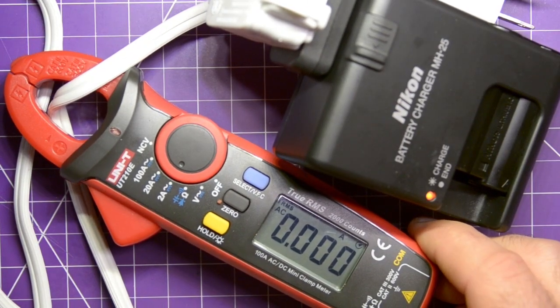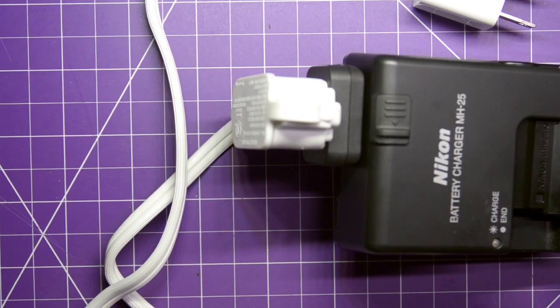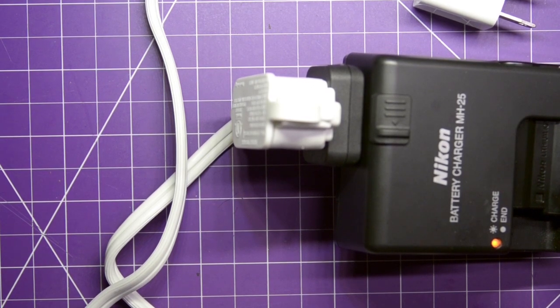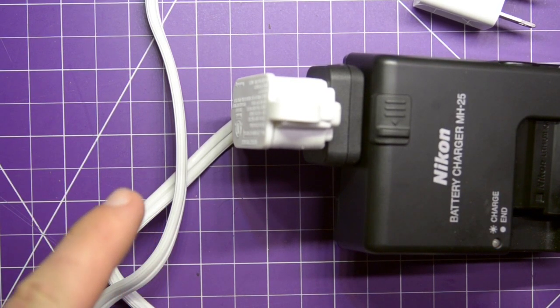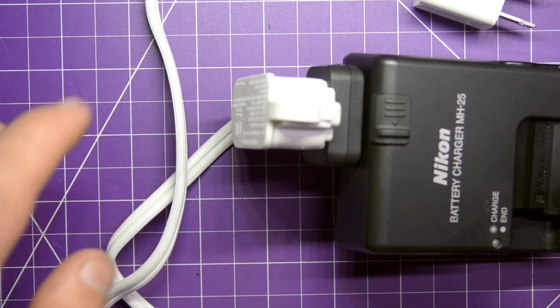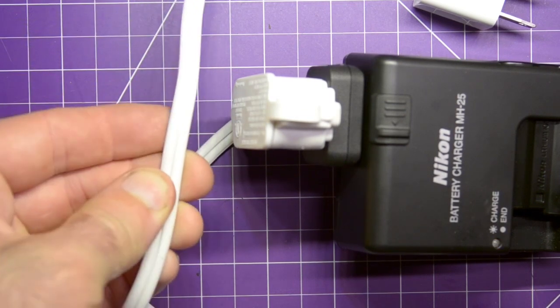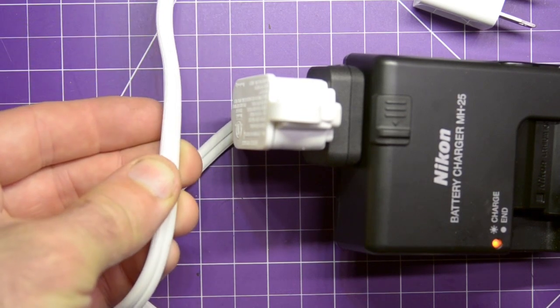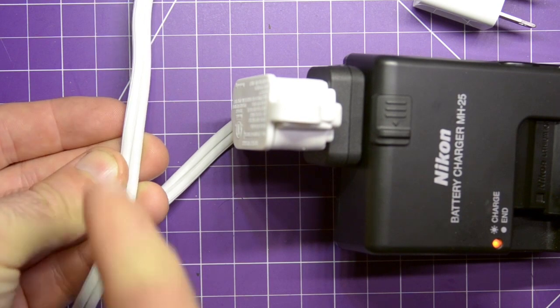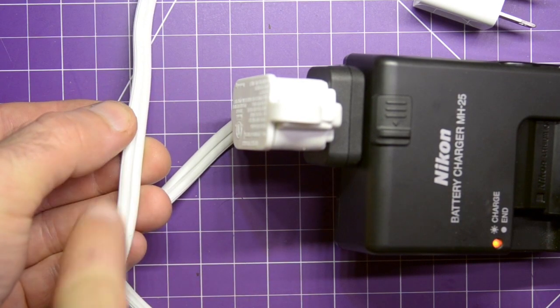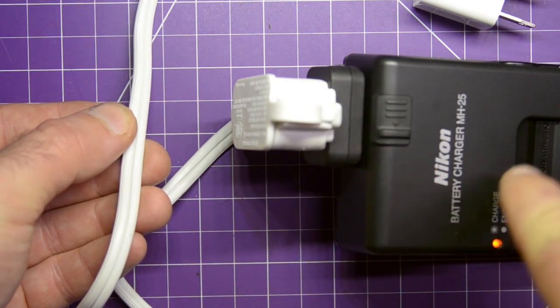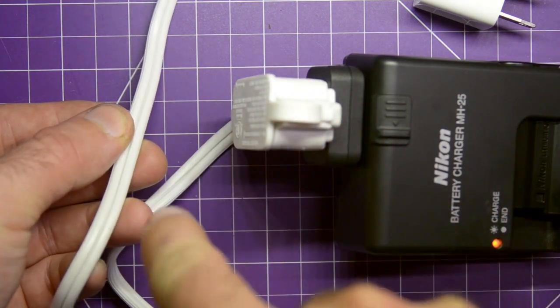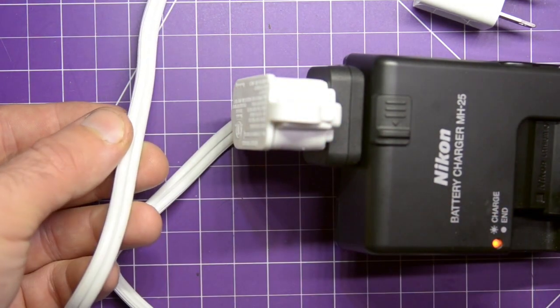Why is it still zero? The answer to that is that the clamp on the amp clamp can only read what's inside the actual clamp. And if you look here, this has two wires on it. So, it has a wire coming from the wall, going through the device, and then coming back out and back into the wall.